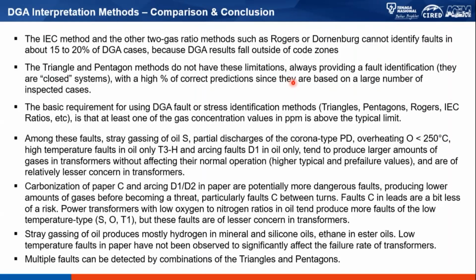So that's the reason why you need to know that this ratio must only be used whenever one of the key gases is above the limit, or perhaps the accuracy is above 10 or 15%. What I'm trying to say is that in TNB we have nearly 2,000 power transformers and 100,000 distribution transformers. We don't have time to look into results which are less than condition 1, perhaps even lower than 10 ppm or 5 ppm. But maybe out there in the industry, you are only looking at 1 or 2 transformers, even 1 or 2 ppm. You are very interested to know the DGA.